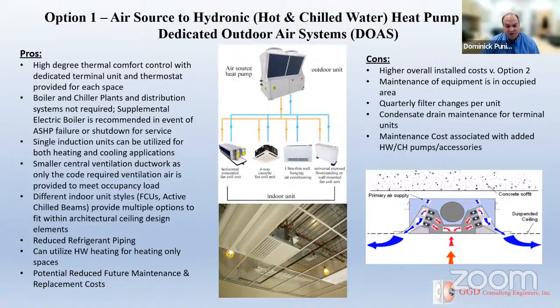And the maintenance is still within the occupied areas. You still will have to do filter changes and maintain the condensate drains. And this is very common for the other options as well. One of the things that the code has done is really push to separate ventilation HVAC from your space heating and cooling loads. So when you have those space heating and cooling loads by fan coils, you will have those maintenance concerns regardless of whether it's a hot water, chilled water system or a refrigeration based system. Next slide.